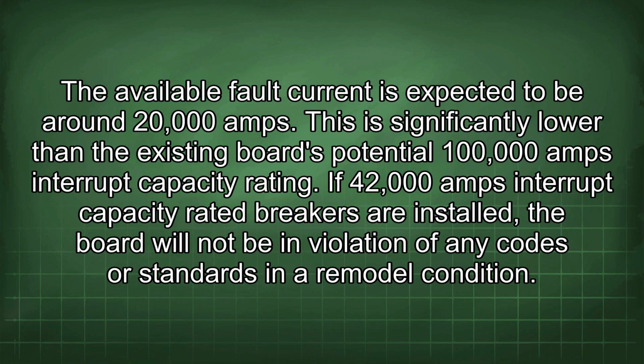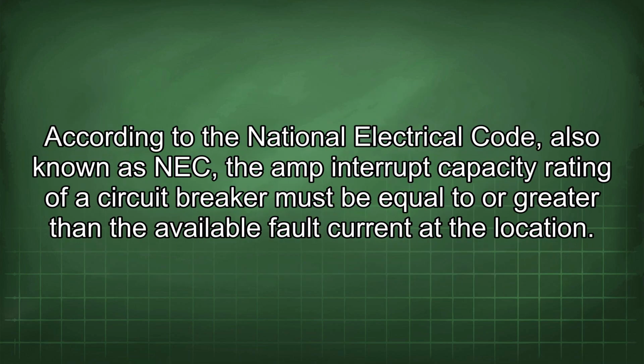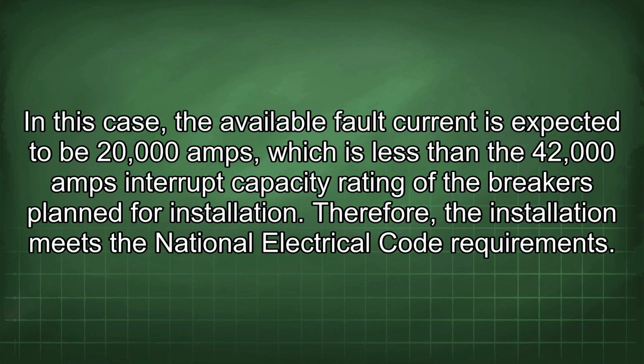If 42,000 amps interrupt capacity rated breakers are installed, the board will not be in violation of any codes or standards in a remodel condition. According to the National Electrical Code, also known as NEC, the amp interrupt capacity rating of a circuit breaker must be equal to or greater than the available fault current at the location. In this case, the available fault current is expected to be 20,000 amps, which is less than the 42,000 amps interrupt capacity rating of the breakers planned for installation. Therefore, the installation meets the National Electrical Code requirements.